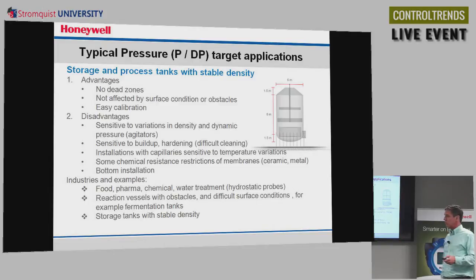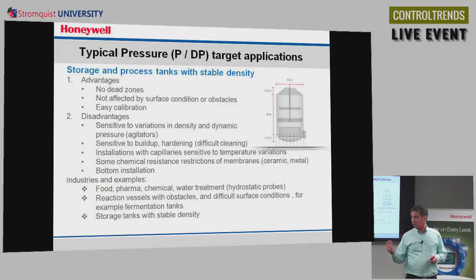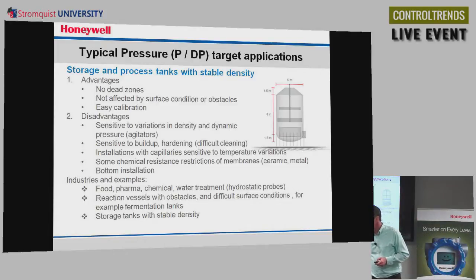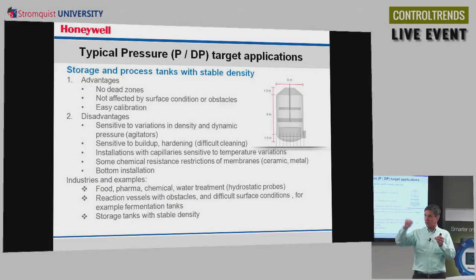It can be sensitive to buildup and hardening on the capillaries, or on the diaphragms. And if you are using capillaries, those can be sensitive to temperature variation. Those big capillaries that I was talking about can be affected by things like just the sunshine. Sunlight will warm up that fluid and cause it to expand, and that can create errors.